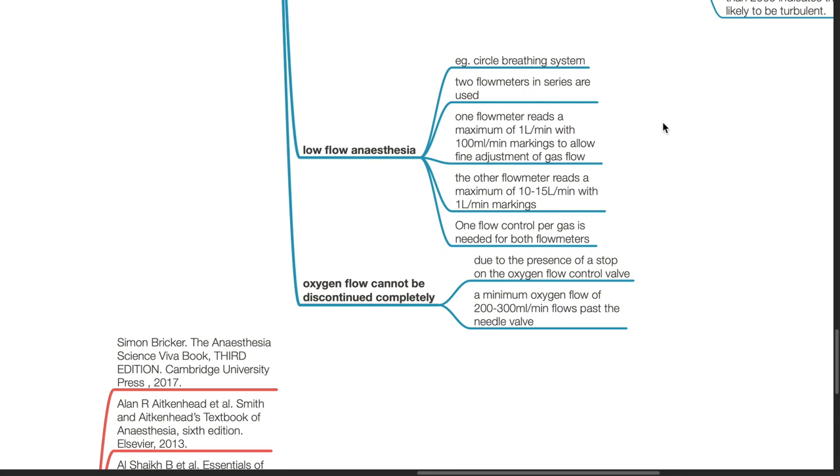One flow control per gas is needed for both flow meters. Oxygen flow cannot be discontinued completely due to the presence of a stop on the oxygen flow control valve. A minimum oxygen flow of 200 to 300 mls per minute flows past the needle valve.